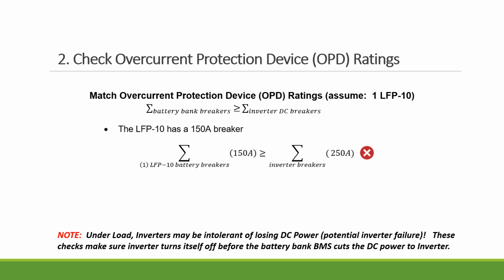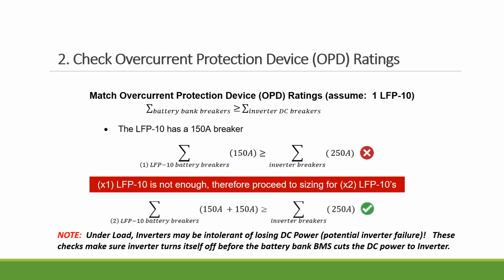In this case, if you do one LFP-10, it has a 150 amp breaker, which is smaller than the inverter breaker. So if a surge comes through, the one LFP-10 will shut off first, and you don't want to see that. But if you do two of the LFP-10 for this particular project, then you're good to go.